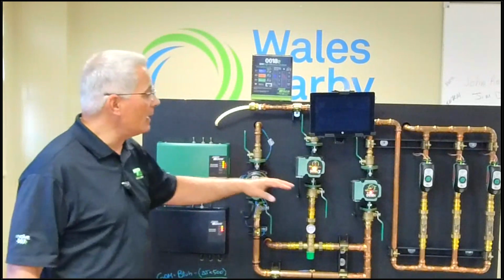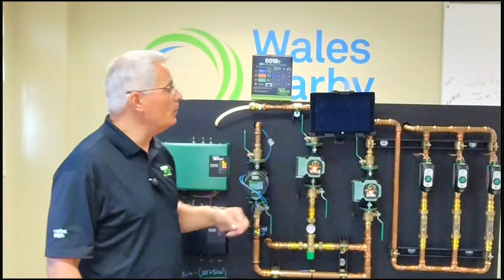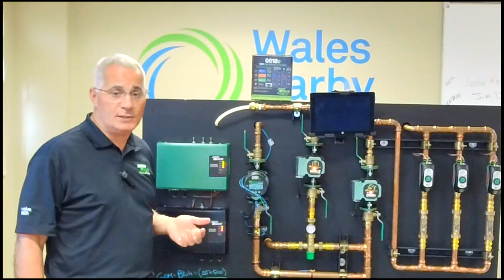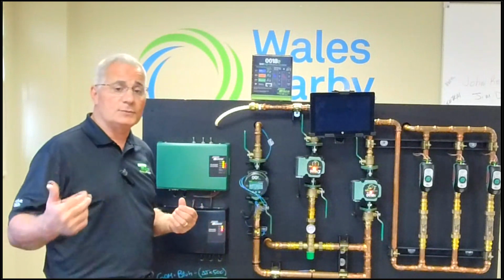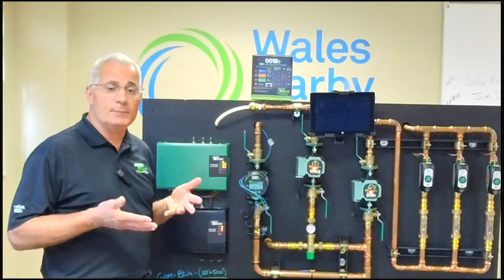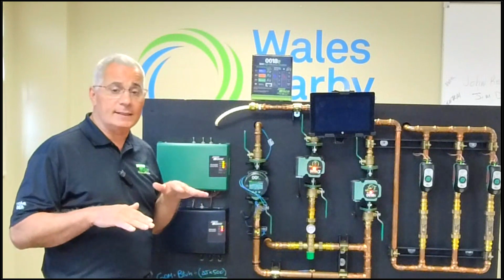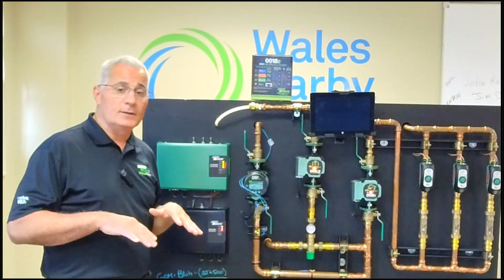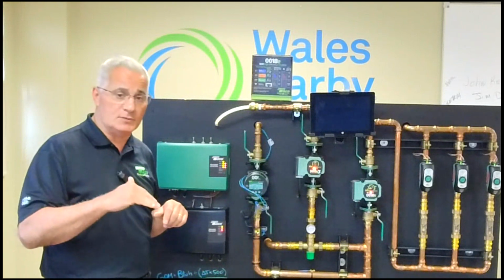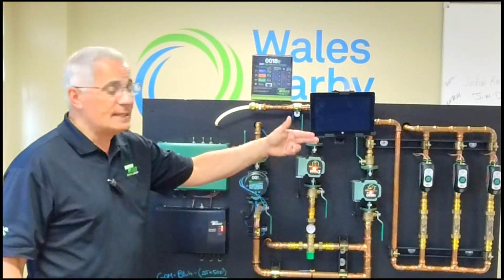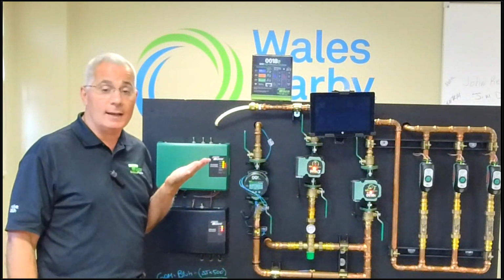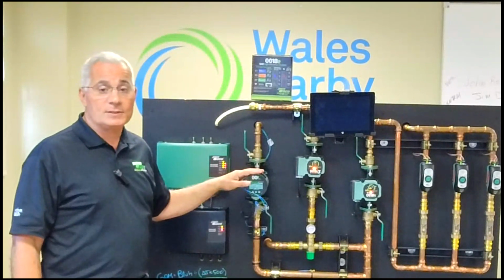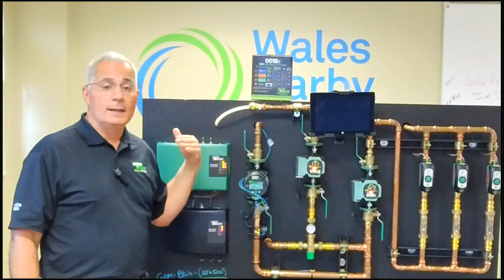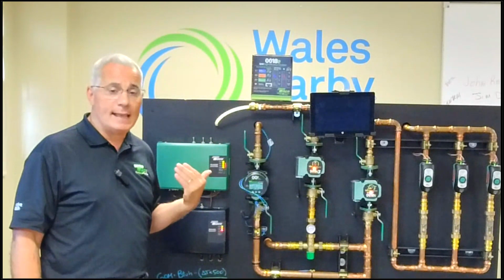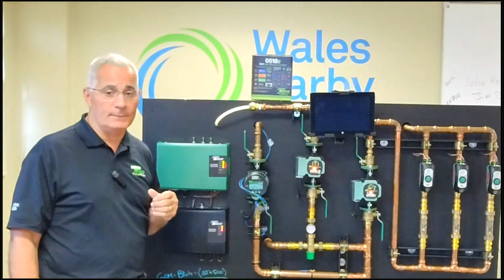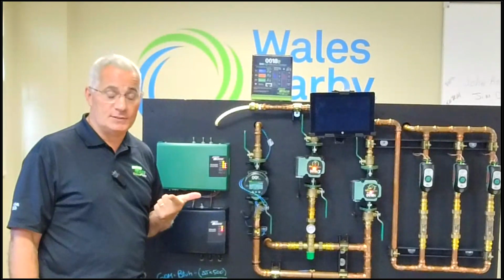So if this circulator was on this system here, as these zones open and close, it will sense that return temperature changing. All zones calling, it will sense that the return temperature is a little cooler, and it'll speed up the pump to get to that 20-degree delta. Once I've matched that, it's going to settle at a speed, more than likely slow down, because that return temperature will be getting warmer and warmer, so it'll keep slowing down. As we satisfy zones, that return temperature is going to come back even hotter, and it will slow down even more. So this circulator here, which is what I have on my system at home, constantly creates a new pump curve. It's matching the pump curve that I need based on the amount of zones calling. Another comfort feature and another energy saving feature.